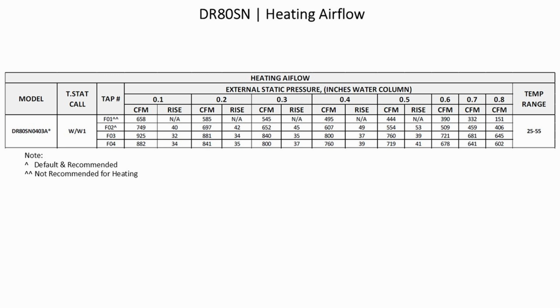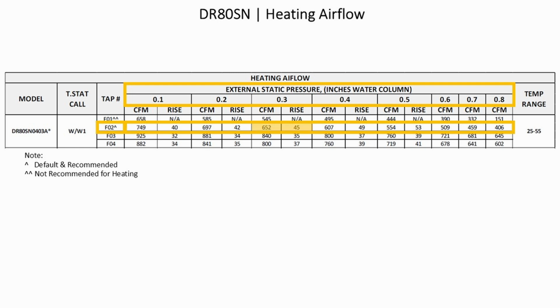The DR80SN heating airflow. For the external static pressure, I've highlighted again 0.1 to 0.8 inches of water column. I've highlighted the default and recommended fan tap of F02, and we're going to show the correlation of CFM and temperature rise to static pressure. So at 0.3 inches of static pressure, the CFM is 652 with a temperature rise of 45 degrees. At 0.5 inches of static pressure, the CFM is down to 554. The temperature rise is up to 53 degrees. The recommended temperature range for heat is 25 to 55 degrees Fahrenheit.